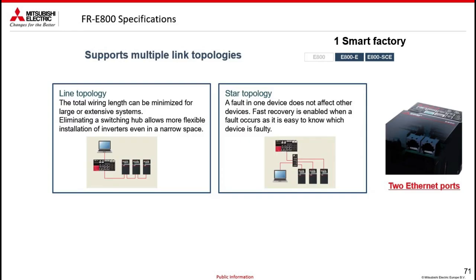The FRE800, unlike the others, supports different types of connections. In fact, the FRE700 inverter with the Ethernet expansion has only one Ethernet port. So you are forced to use an Ethernet switch to be able to connect the different slaves under the hypothetical master, which will be a PLC or whatever it will be. The FRE800 on the other hand has a double port, so it allows you to do both the ring type connection, so the in-out, rather than the star type, so a classic switch, and then go to the other devices.